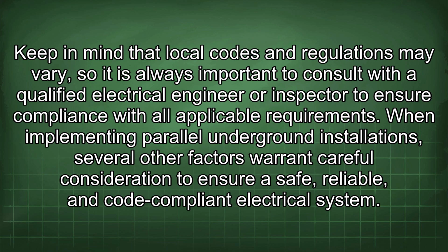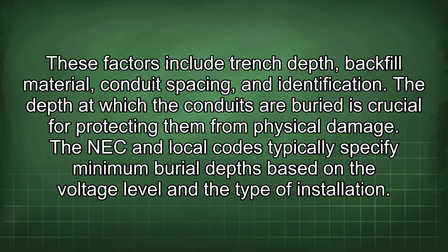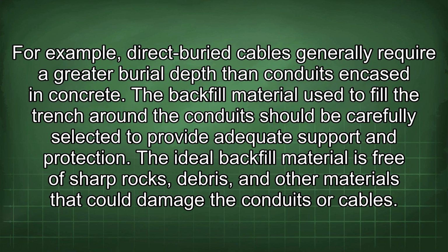When implementing parallel underground installations, several other factors warrant careful consideration to ensure a safe, reliable, and code-compliant electrical system. These factors include trench depth, backfill material, conduit spacing, and identification. The depth at which the conduits are buried is crucial for protecting them from physical damage. The NEC and local codes typically specify minimum burial depths based on the voltage level and the type of installation. For example, direct buried cables generally require a greater burial depth than conduits encased in concrete.